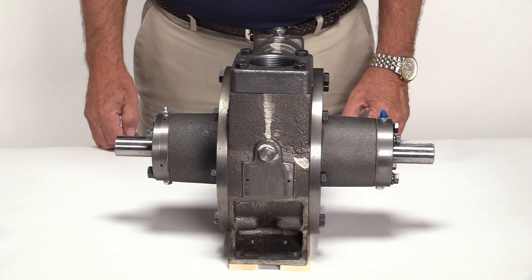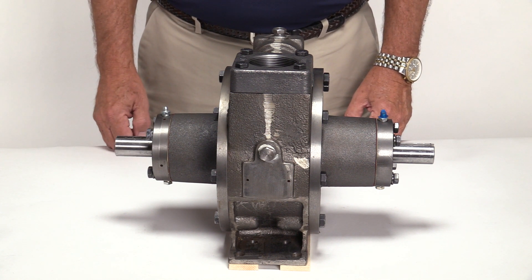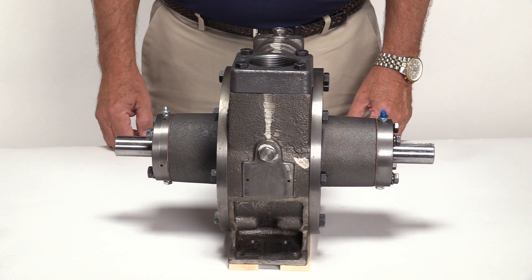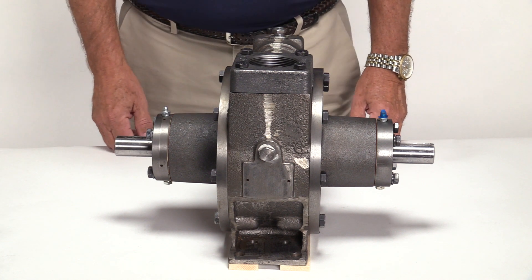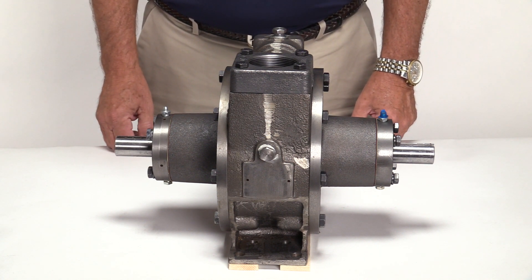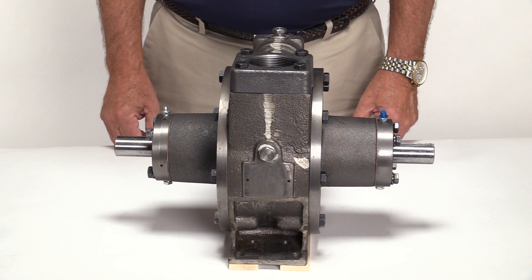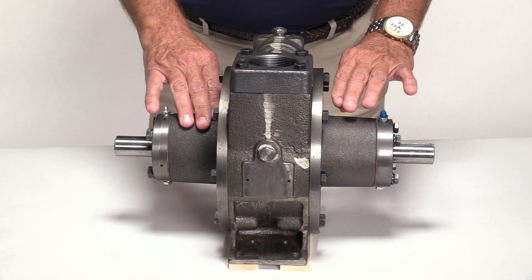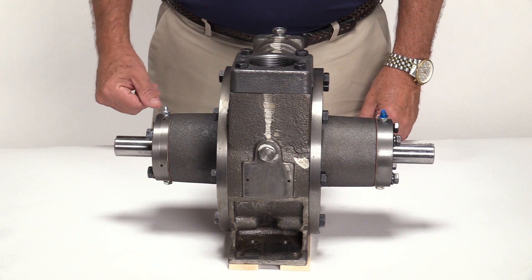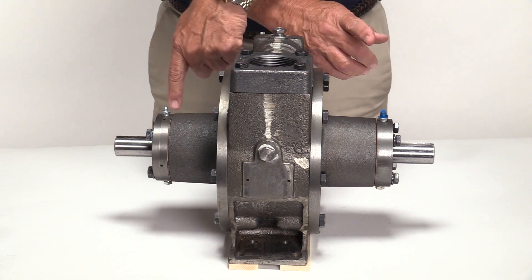Typically, the only time a Corken sliding vane pump is shimmed is before it leaves the factory, after installing major components, or installing a full rebuild kit. Since rebuild kits include a rotor shaft assembly, cam, side plates, and cover, the stacking order of these parts may differ from the original parts, causing the rotor to rub against one of the side plates. To ensure the proper clearance between the rotor and side plates, shims are added to each bearing cap. The shims keep the bearing caps from pushing the rotor into the side plates or thrust bearing assembly on the opposite side. Note that shimming is not required after installing a Corken repair kit. However, if the rotor shaft assembly is reversed, the pump must be re-shimmed.